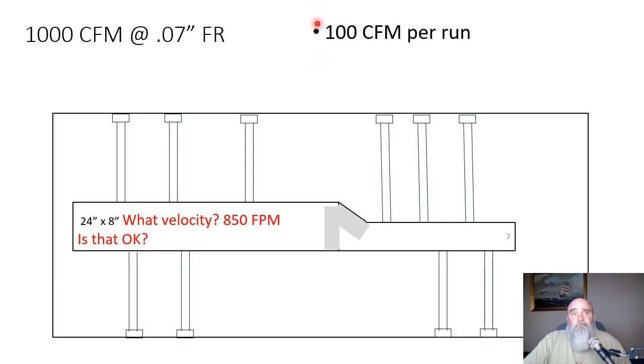So our velocity was 850. Is that okay? And the answer to that is yes. Our maximum velocity in a supply trunk as per Manual D is 900 feet per minute.